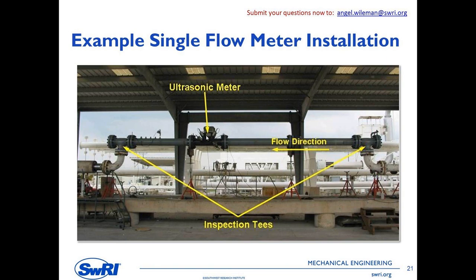So this is a simulation of how the thing's actually going to be installed in the field. The difference here is it's probably going to be sitting on a header, not directly on these little elbows that lead into the inspection tees. So that's one difference that might occur between this installation and the actual field installation. But at least you're capturing some of the last effects of the piping installation before going into the meter. And that can be important.